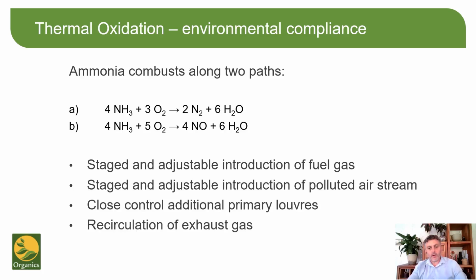Emission compliance requires the thermal oxidizer to be able to be adjusted so that the ammonia combusts along path A and not path B, reliably and without fluctuation. To ensure this, we have various aspects of the combustion that we can tune to suit the gas and site conditions. We can adjust whether the fuel gas is introduced all at one level or that we stage the burn over two levels. We can balance how the ammoniated air is introduced to the thermal oxidizer, either below the burn, where it will be mainly primary combustion air, or during the burn, where it will be mainly secondary and tertiary air. Any additional primary air we allow into the thermal destructor is very closely controlled so as to keep the combustion temperature within a very narrow band.